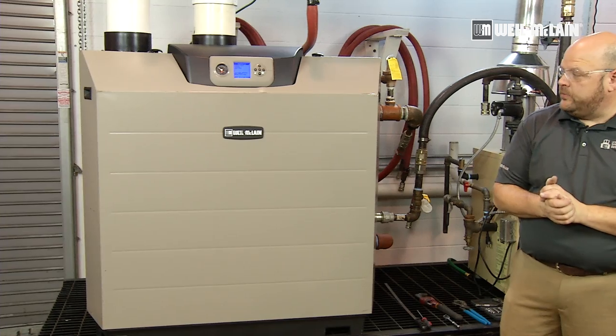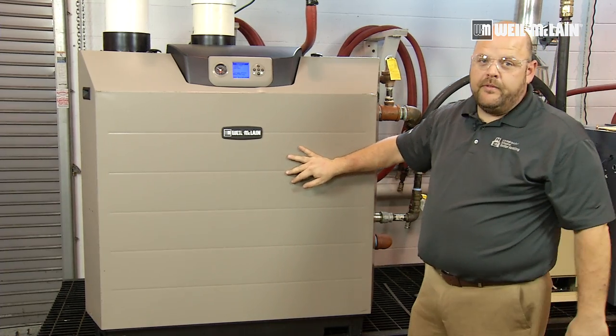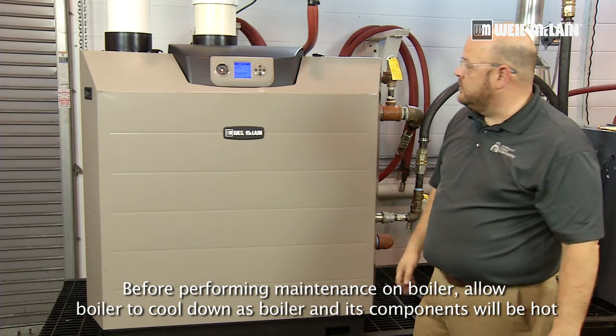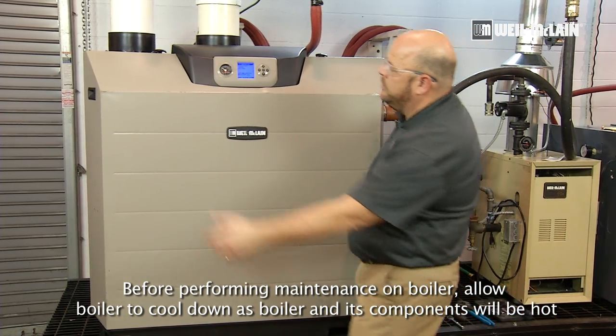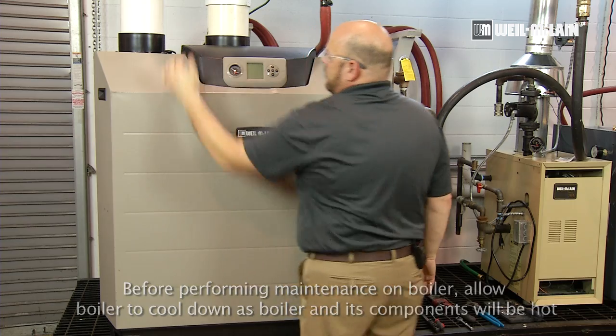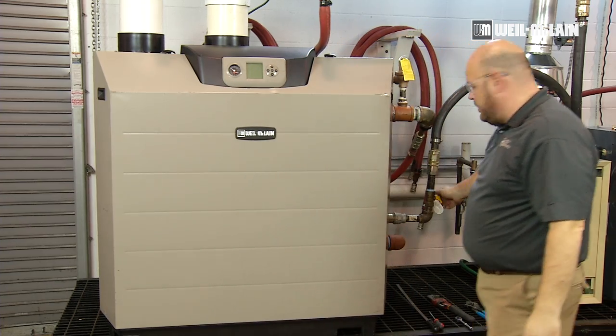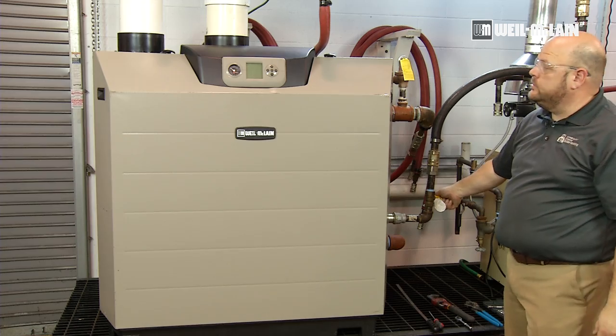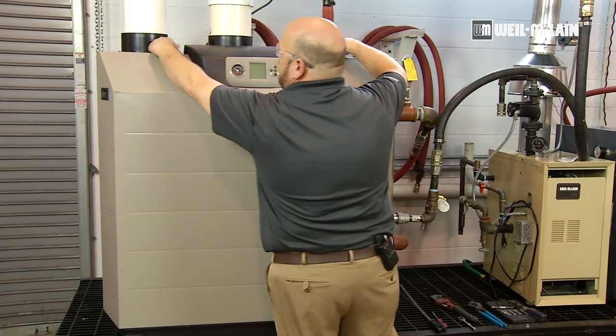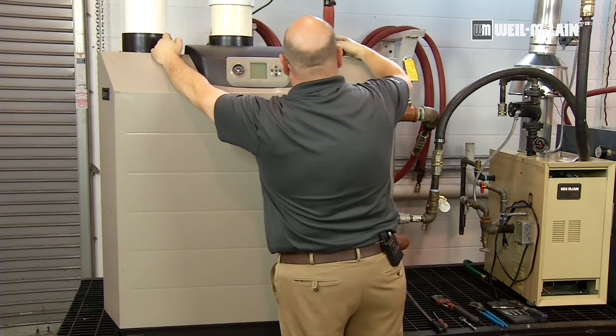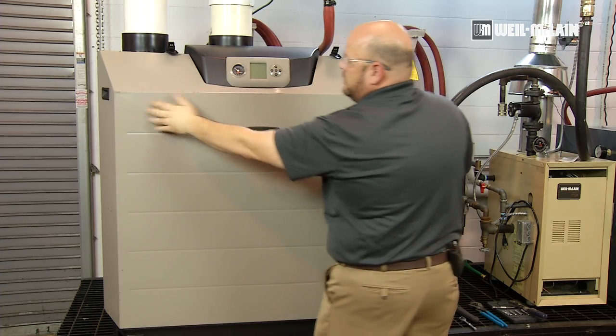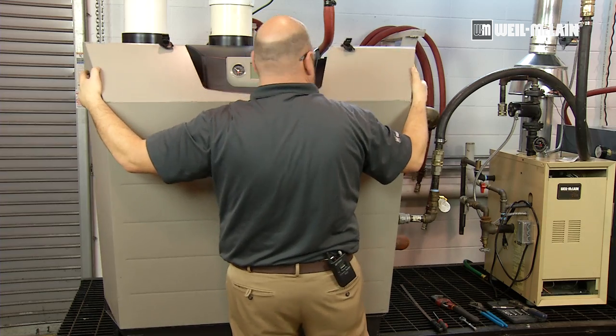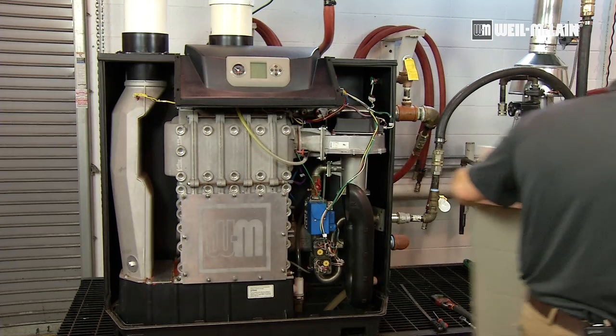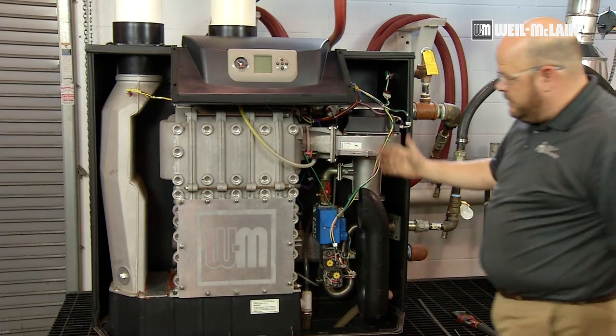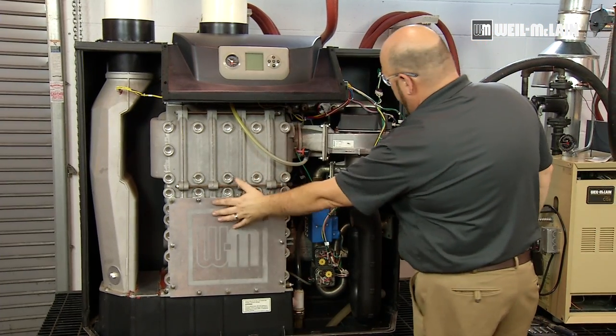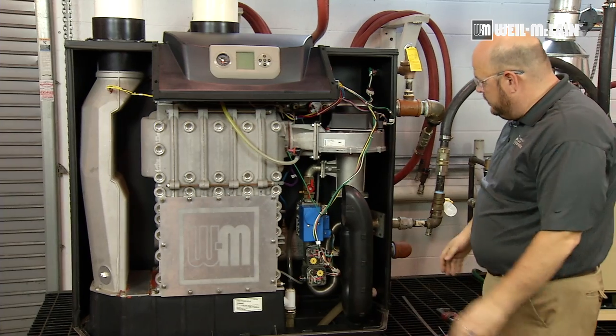In this video, we're going to demonstrate how to clean the SlimFit 550 and 750 heat exchangers. First, we'll start off by shutting off the power to the unit in the back corner, and we will shut the gas off to the boiler. Then we'll remove the front jacket by lifting and twisting the two latches, leaning back the panel and removing it from the unit. This allows us to gain access to the inside of the boiler, the heat exchanger, and the combustion assembly.